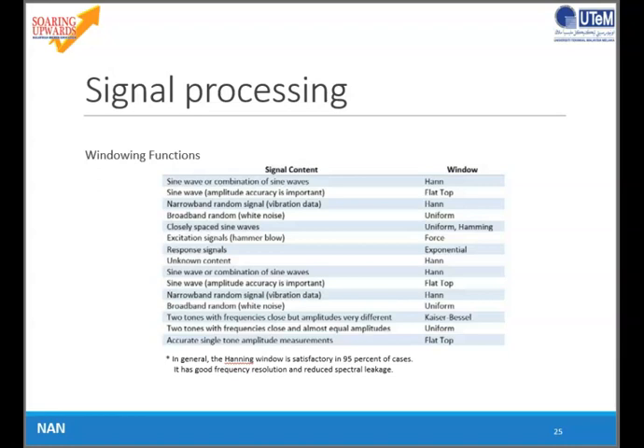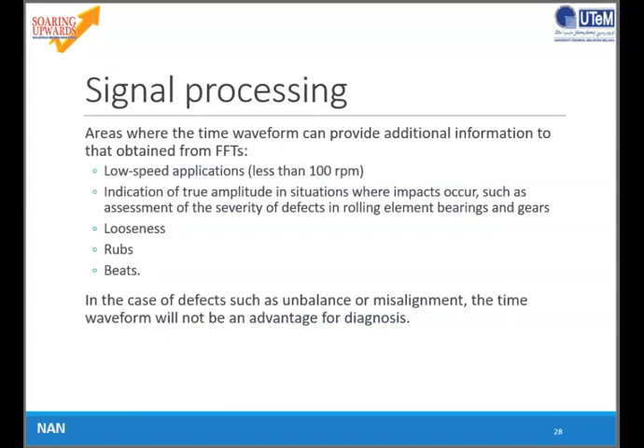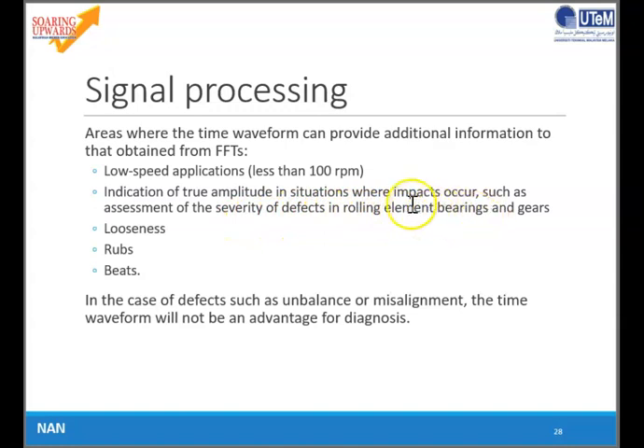Next is signal processing. Areas where the time waveform can provide additional information beyond what is obtained from FFT include low-speed applications below 100 rpm, and indication of true amplitude in situations where impacts occur, such as assessment of the severity of defects in rolling element bearings and gears, and also for looseness, rubs, and beats. In the case of defects such as unbalance or misalignment, the time waveform will not be an advantage for analysis. Normally we convert the time waveform into a spectrum for further analysis.